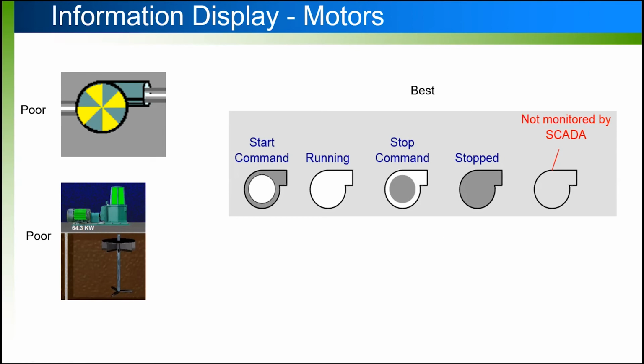When something is not monitored by SCADA, but it's important to a process, you can fill it with a background color, right? That'll show the operator that it's there. It may or may not be helpful in terms of troubleshooting. Let's say a valve is located in your pipeline, but you don't know its status, you can still show it on your HMI screen. And if you're not getting flow, it could be based on that valve's position.